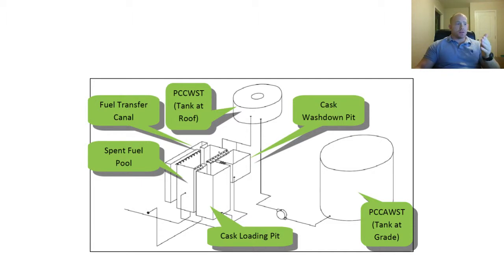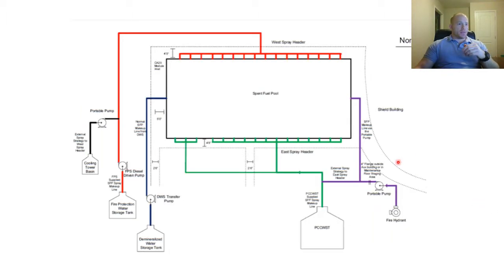And then when all else fails, there are a number of systems that can also provide cooling water. From the cooling tower basin, you can throw in river water or seawater. You can use the fire protection water storage tank, which is on site, and this pump. You can use the demineralized water storage tank and this transfer pump. You have the tank that was at the top of the structure. You can also bring in a portable pump and use the fire hydrant. So there are a number of sources of water to provide cooling to the spent fuel pool.